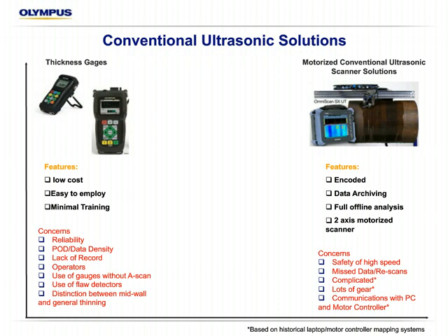If we're only going to use a conventional small sensor in order to make that profitable for the NDT company or even in-house doing your own corrosion surveys, you typically have to move at a very, very rapid speed. And in a lot of our industries, we know you walk into a refinery or some kind of processing plant, almost every moving part has a guard around it. Safety is, I think, everybody's main concern as far as corporate ethics and company policies. So to have something screaming at a very high speed in order to make it productive is kind of counterintuitive.